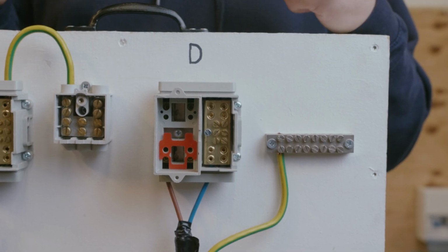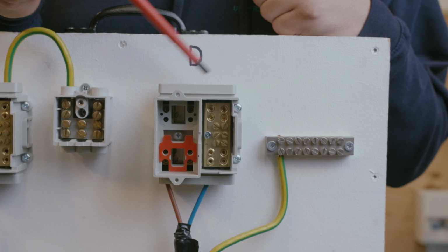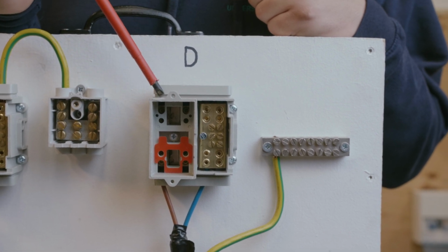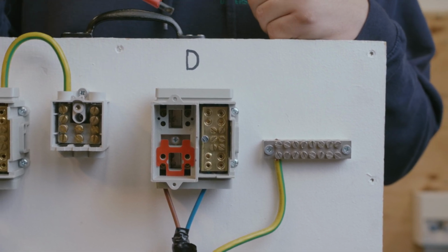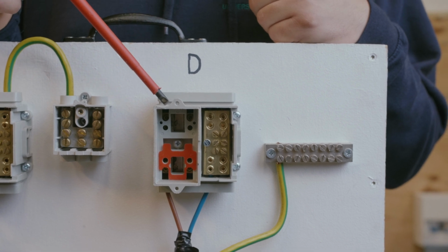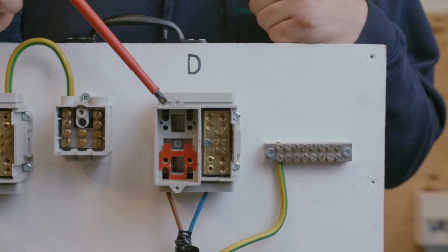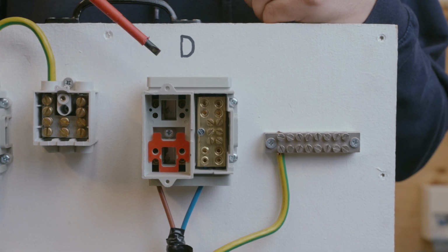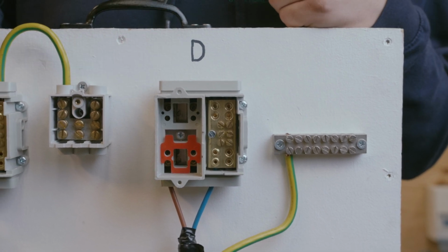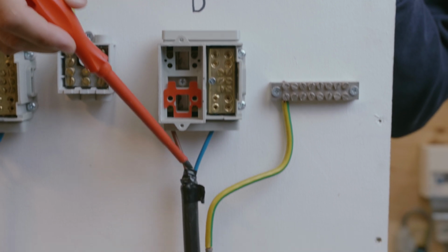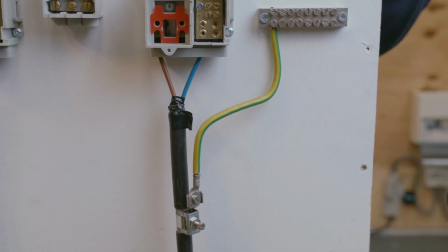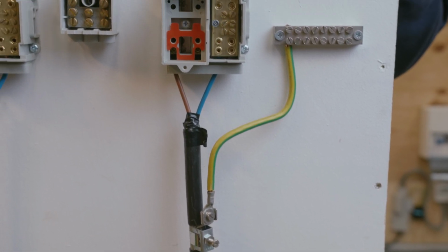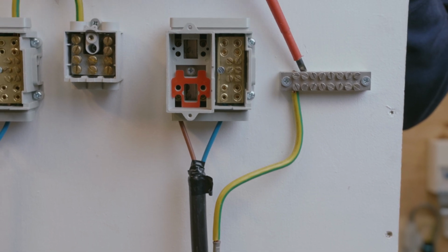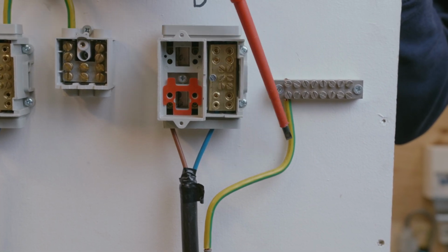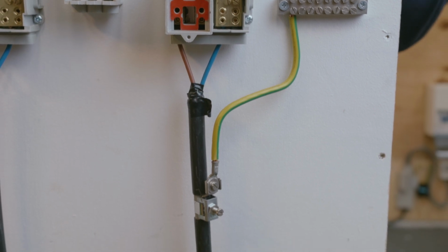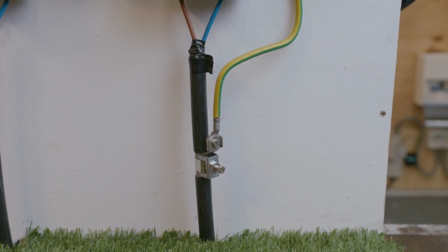So as you can see, this setup here on D is actually the same as A, so it's still a TNS. So Terra being T, neutral, and S for separate, so TNS. Okay, the only difference is this service coming in is a 2-core cable coming in, so you've got the line conductor and the neutral. The earth is on a separate bar like we've shown on here, but it's actually connected to the steel wire armouring of that supply cable there.